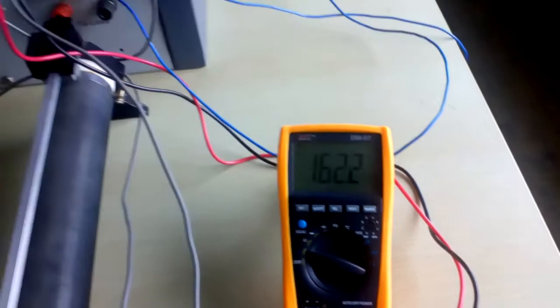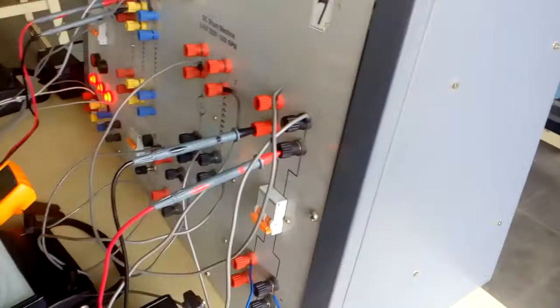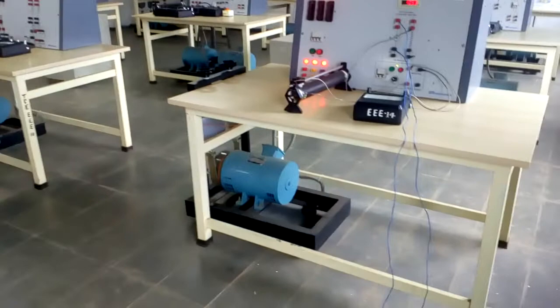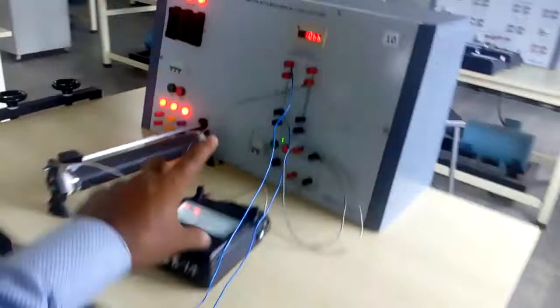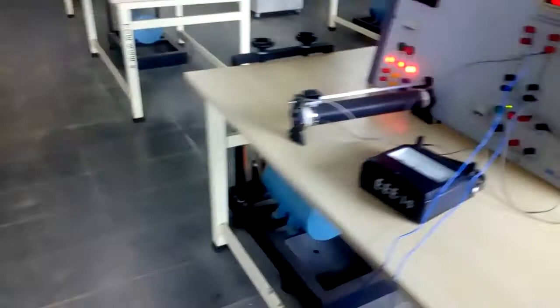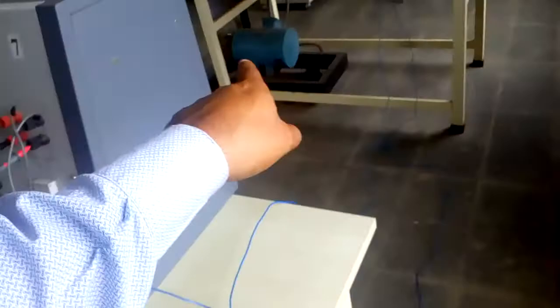Now we switch on the switch so that the generated DC voltage supply is given to the motor armature. The motor starts to rotate in the reverse direction. To rotate the motor in the forward direction, you have to interchange either the two terminals of the armature supply connections. Now we will control the speed of the motor using the rheostat of the generator — by increasing the field excitation of the generator, the generated voltage increases and therefore the speed of the motor increases.